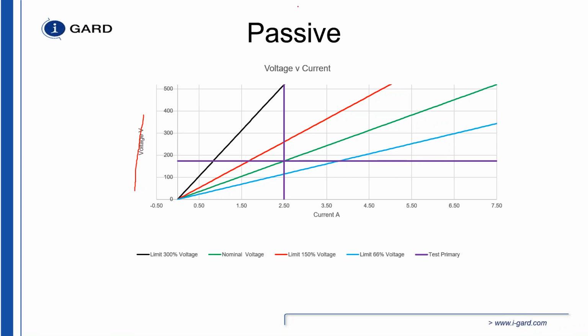So our limits when you have this type of system in passive is we can monitor 66% of the resistance to 150% of the resistance. And for some of our relays, we can actually monitor 300% resistance. This line defines the 300% resistance change.